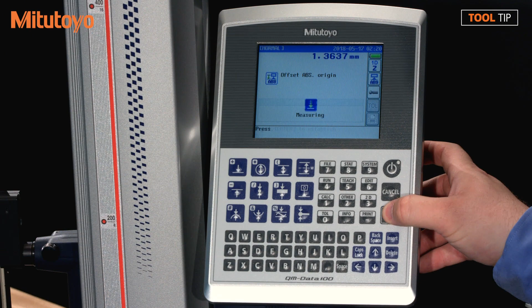And that's very easy to do, but what if I don't have a Checkmaster like this? Well, you could use a stack of gauge blocks, or you could use a master part that has a certified value. So again, even if I'm using gauge blocks or a master part, always go back to the certified value. Yeah, always use that certified value. The whole point of this is you're zeroing the probe position. If the probe position isn't accurate, then none of your height measurements will be either.